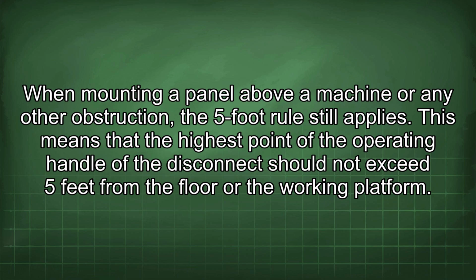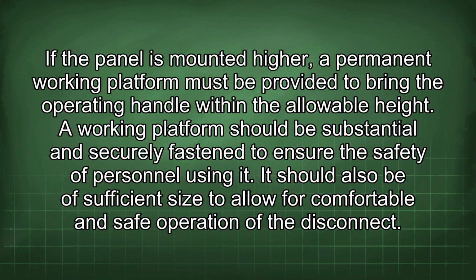This means that the highest point of the operating handle of the disconnect should not exceed 5 feet from the floor or the working platform. If the panel is mounted higher, a permanent working platform must be provided to bring the operating handle within the allowable height. A working platform should be substantial and securely fastened to ensure the safety of personnel using it. It should also be of sufficient size to allow for comfortable and safe operation of the disconnect.